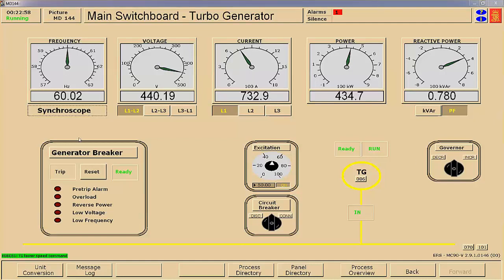Now, one of the things you notice here is that I'm a little bit high on the frequency, so I may do a couple clicks on this and get it slightly below 60. So you're going up and down right at the hertz mark, and then keep going back and forth. Again, I'm adjusting the governor on number 2 up and the governor on the steam turbine down. And I'm watching my power, and as soon as it gets down around 20k, then I'm going to take it off the line.